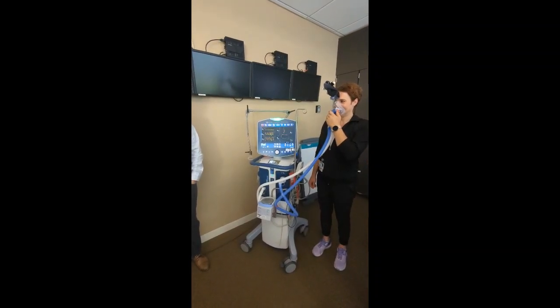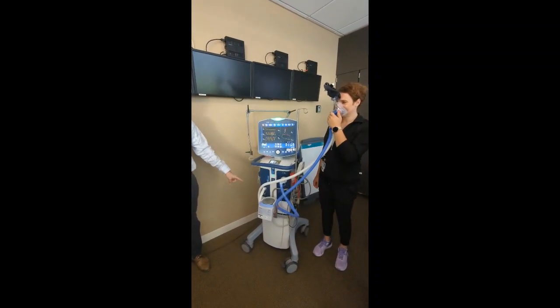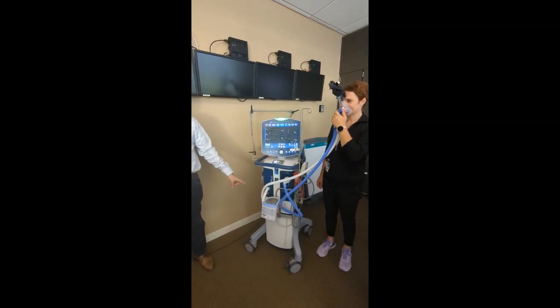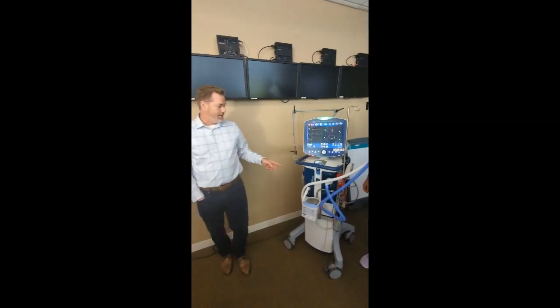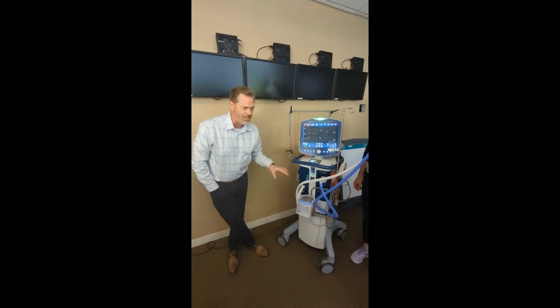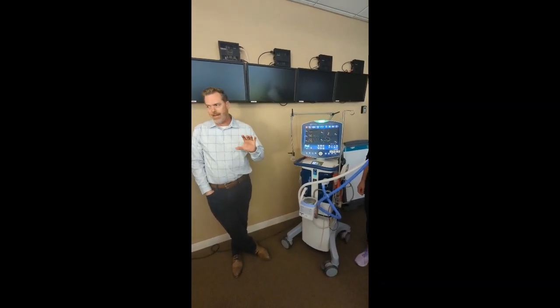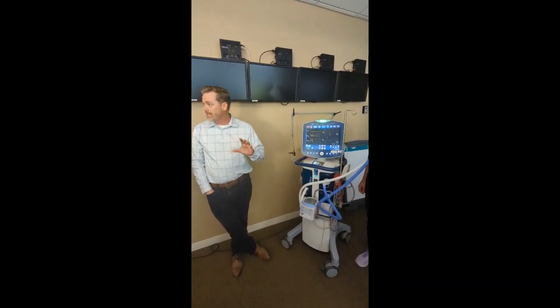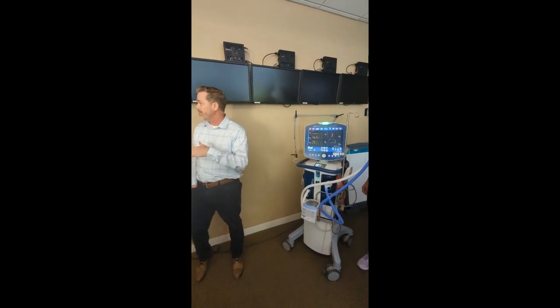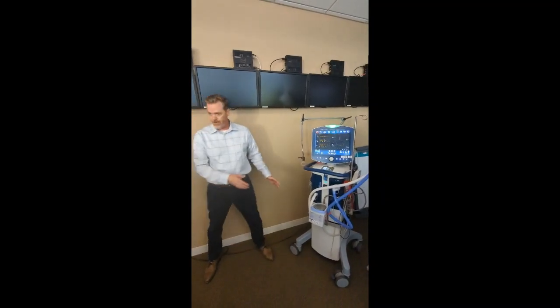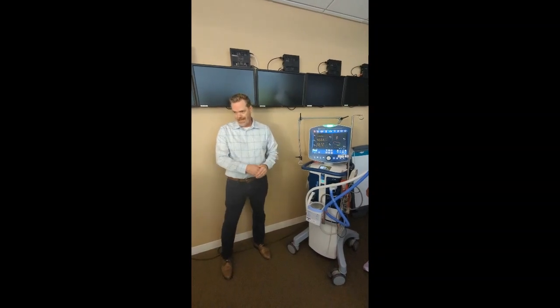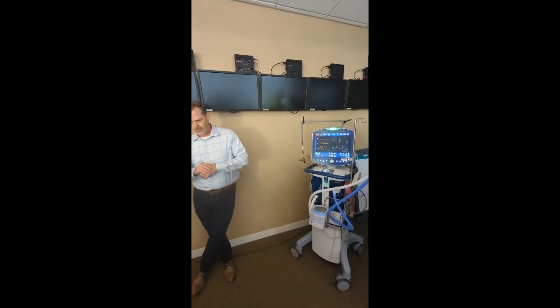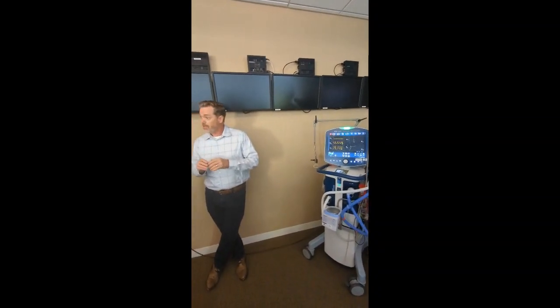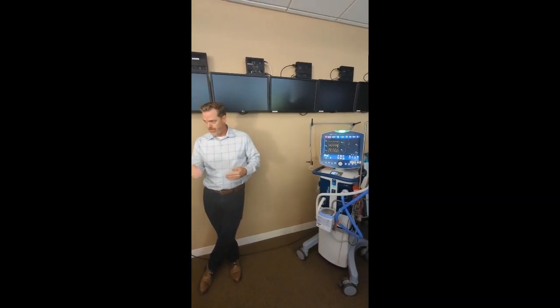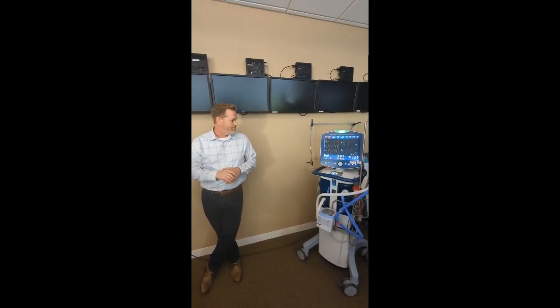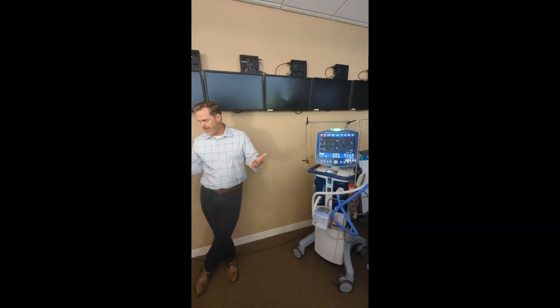The other part of this, on the sample line, the compressor is working pretty hard, right? We have a filter on the sample lines. Note that if you're using that compressor, it will only generate about 35 liters of performance. We said that we can manage a 65-liter leak on a ventilator, but if you're just on the wall, anything over 35 liters, and it's really pushing it. It'll try to do it, but you might have some performance issues. So most of the time it'll be plugged into everything, so it should be fine.